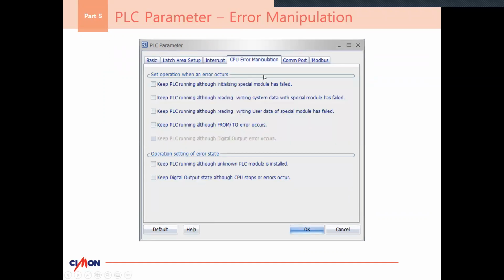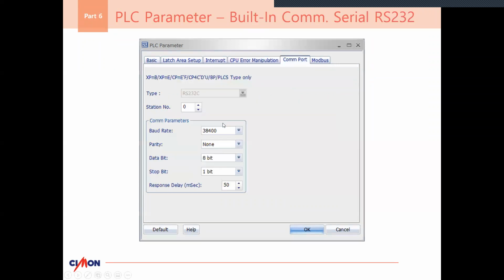So if you deem that an error is okay, that an error will not hurt someone, you can always bypass those errors. And you can do so here in the PLC parameter, so you can keep the PLC running if one of the modules has failed, if a from-to error occurs. If any of these errors occur, you can keep it going through that error by coming here and then checkboxing one of these boxes. Otherwise, I would be very careful on how you use these boxes.